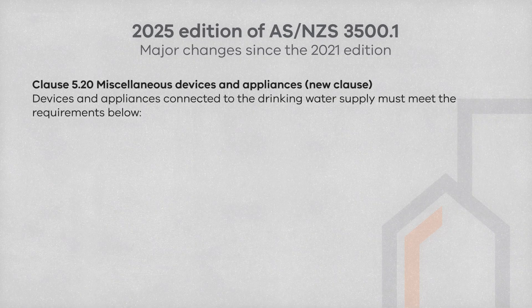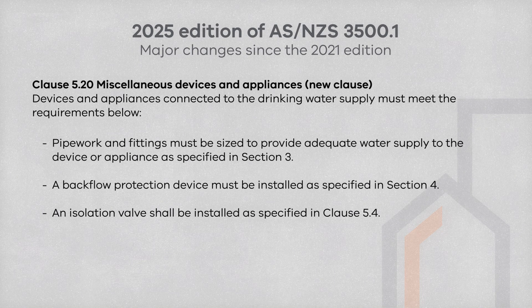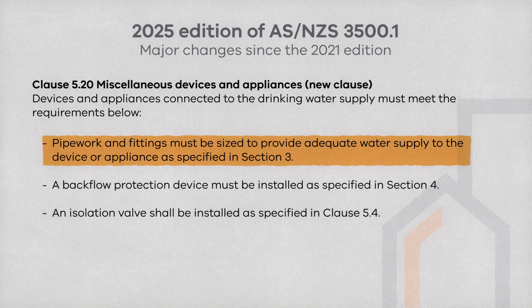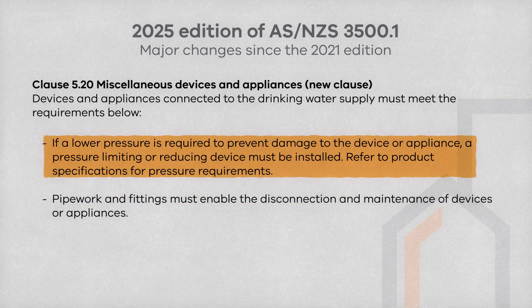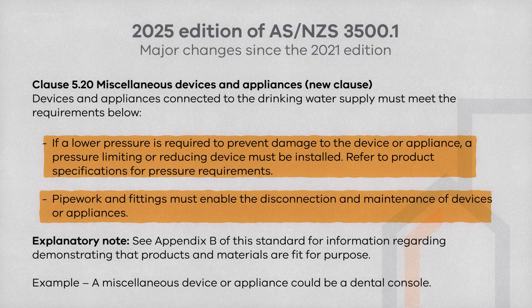A new Clause 5.20 covers the requirements where miscellaneous devices and appliances are connected to drinking water supply. Pipework and fittings must be sized to provide adequate water supply, appropriate backflow prevention devices, isolation valves, and pressure limiting requirements where required. The installation must also allow for the disconnection and maintenance of those devices and appliances. An example of a miscellaneous device or appliance would be a dental console.